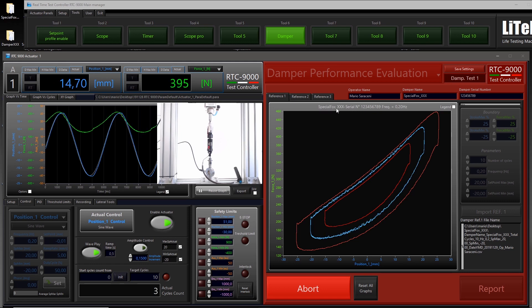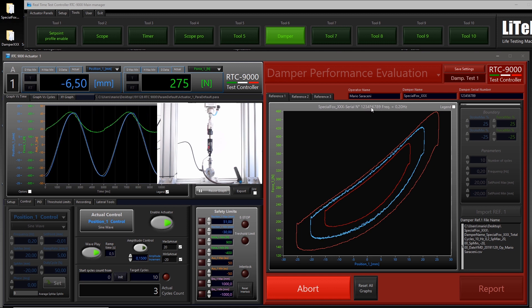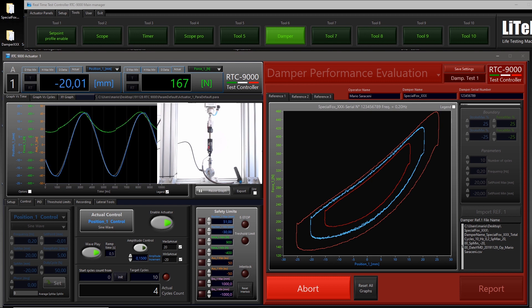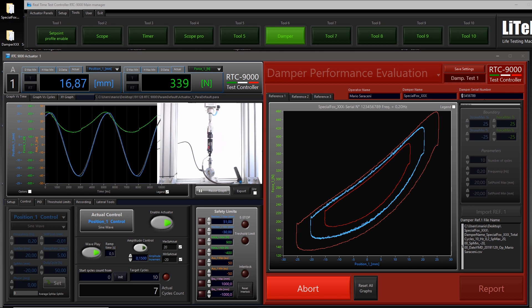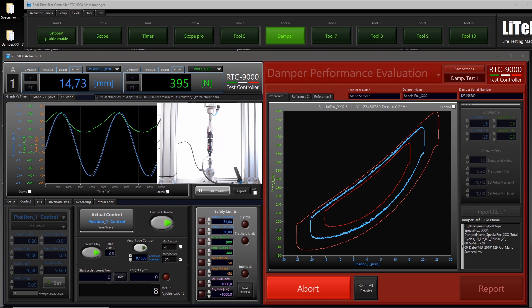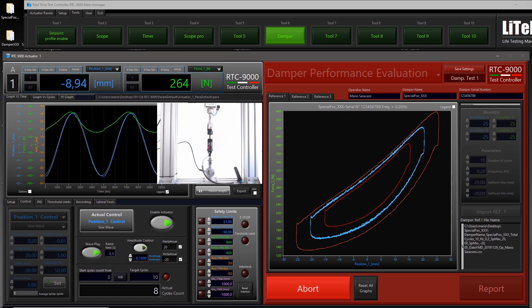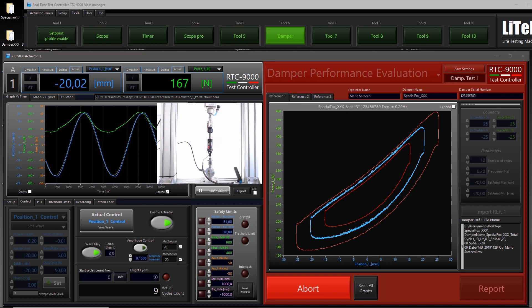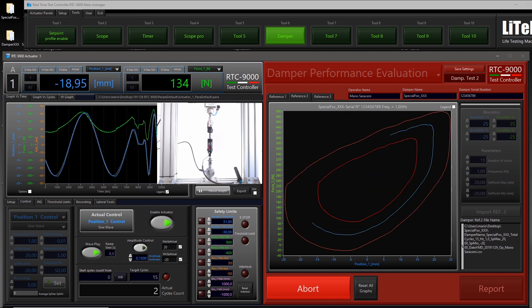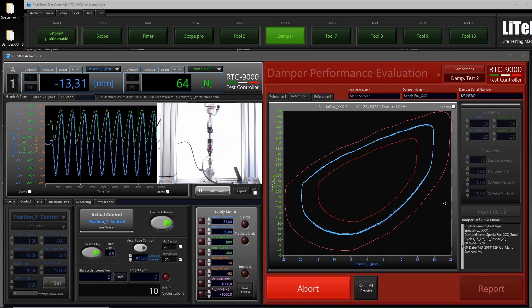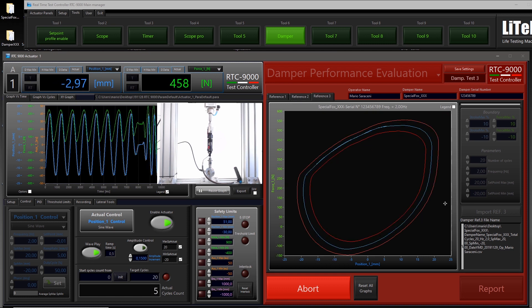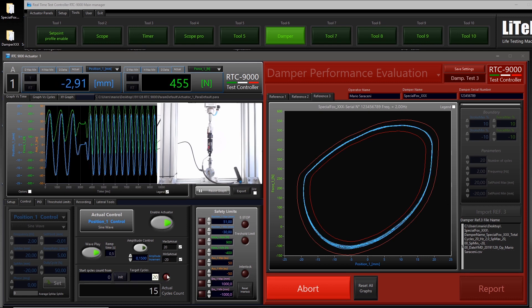Remember the first two seconds are trimmed. Here we have the type of the damper and the serial number — always enter the serial number because this is the new damper under test and the report should include it. This is the second reference test running, and then the third reference test with the target of 20 cycles.